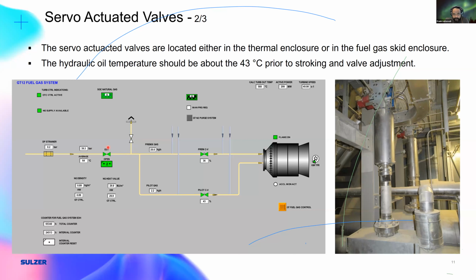And if you're unable to vent, it means that you would either need to vent into the machine or break the pipe before, which means that in a scenario where you're performing an outage, you are actually introducing combustible gases into the combustion chamber, which is something you want to avoid, because you just need a spark from a welder or something happening in there, and then you have an explosion once you exceed the lower explosion levels.